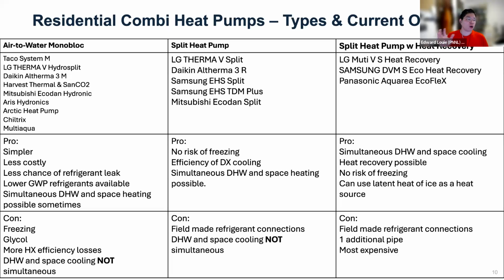And with the refrigerant all located outside, the monoblock system, under the current refrigerant regulations and upcoming regulations, has more low GWP refrigerants available. Those refrigerants are flammable or somewhat flammable. There are debates on whether they should go inside the building. It's interesting, that discussion, because we have natural gas going inside homes and people park cars with whole tanks of gasoline in their garages. So whatever. We can go to the next slide.